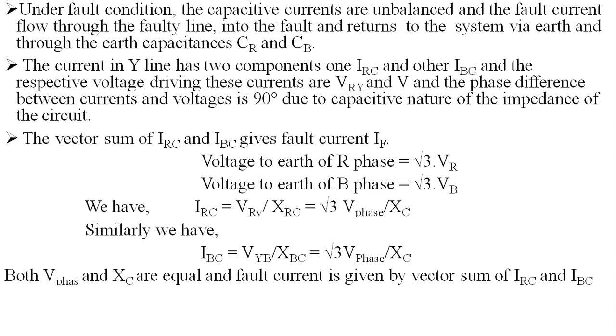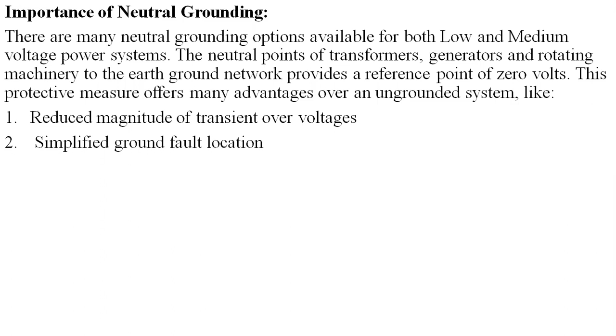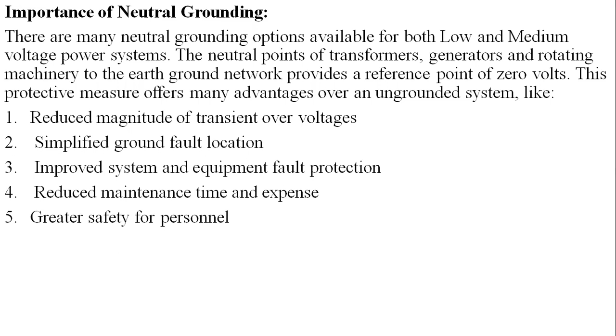Importance of neutral grounding. There are many neutral grounding options available for both low and medium voltage power systems. Connecting the neutral points of the transformers, generators, and rotating machinery to the earth ground network provides a reference point of 0 volts. This protective measure offers many advantages over an ungrounded system, like reduced magnitude of transient overvoltages, simplified ground fault location, improved system and equipment fault protection, reduced maintenance time and expense, greater safety for personnel, improved lightning protection, and reduction in frequency of faults.